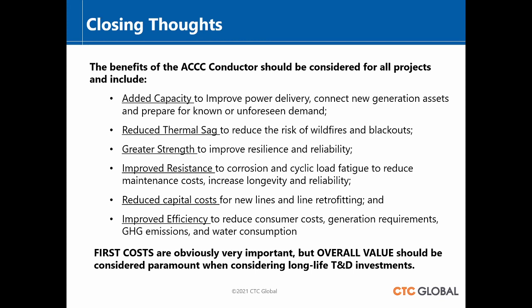It's greater strength, the core is stronger, both for reliability and resilience. Resistance to corrosion, reduced capital costs. When you need capacity and can put this on existing structures, it's the lowest cost solution for capacity. And improved efficiency: on a per-diameter, size-for-size comparison, you're going to pick up 30%, 25 to 40% more efficiency. Reduced line losses, and all that goes with that: generation requirement reduction, emissions reduction, and water consumption.